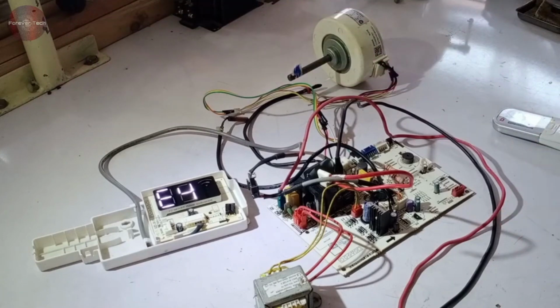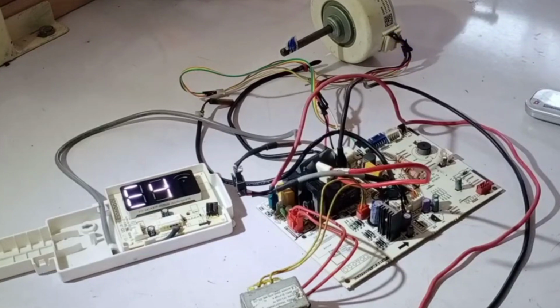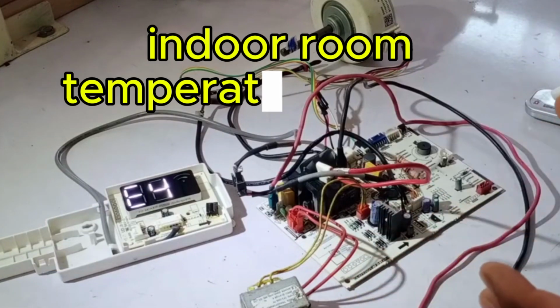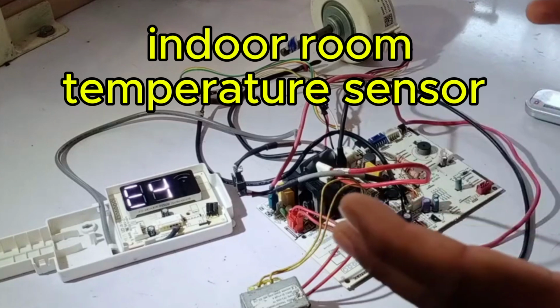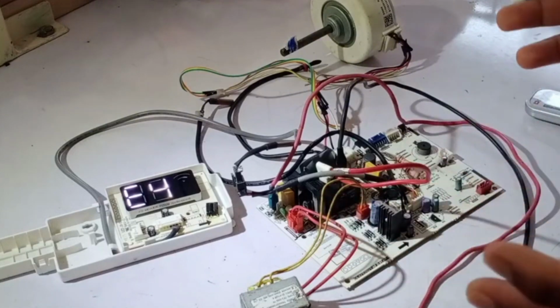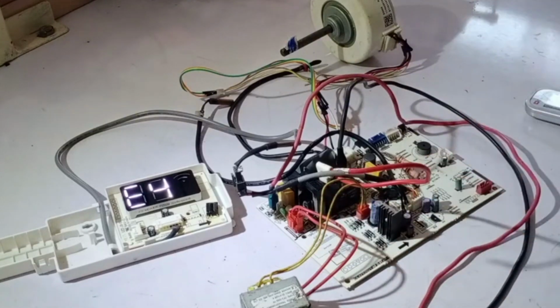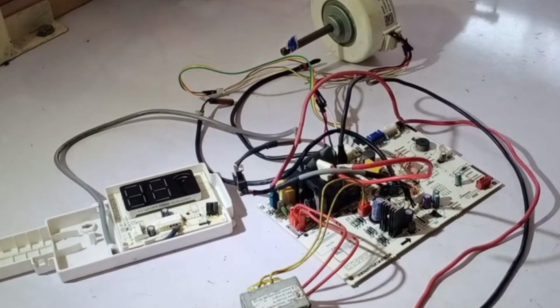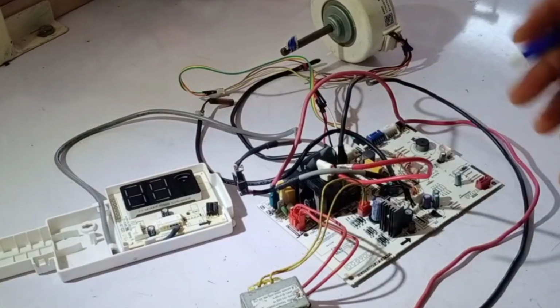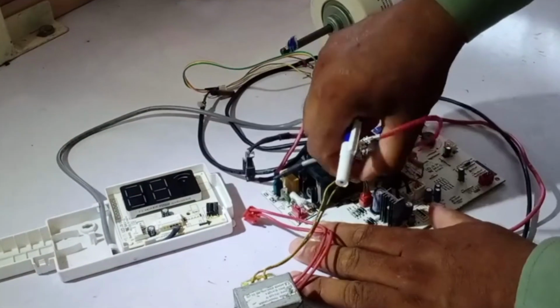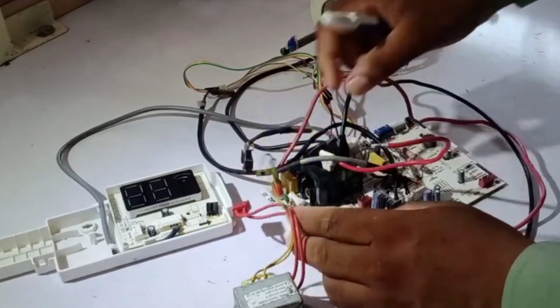This particular error occurs only in non-DC inverter units. Whenever an E4 error appears, it means that the indoor room temperature sensor has become faulty or has short-circuited for some reason. In such a case, the unit will display the E4 error. Right now, we have turned off the power to the PCB, and I will explain more possible causes of the E4 error. I will remove some components so that I can show you a closer view.